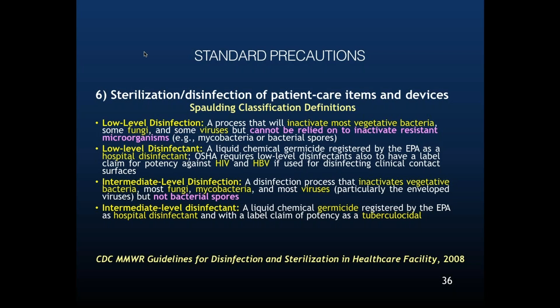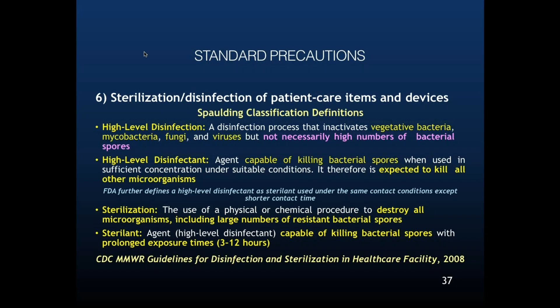And the problem with high-level disinfectants is not every spore gets killed. So the reason we choose sterilization and spore tests is because that will verify that we're killing everything, including spores. That's what it boils down to. So yes, you can use intermediate and high-level disinfection for your low-risk and intermediate-risk things, but when it comes to these critical items, you must sterilize, period. That's what this all boils down to.